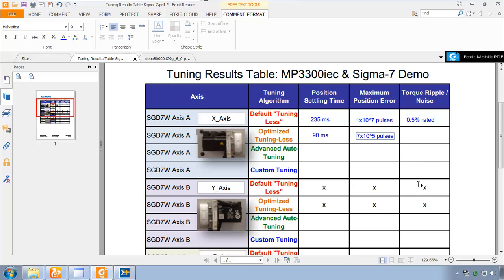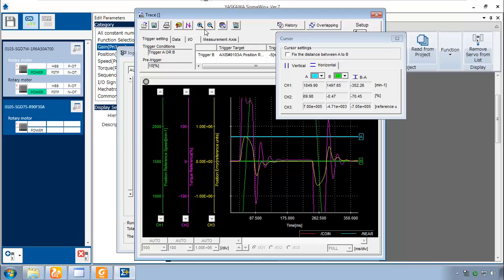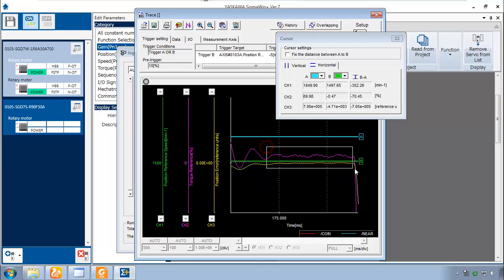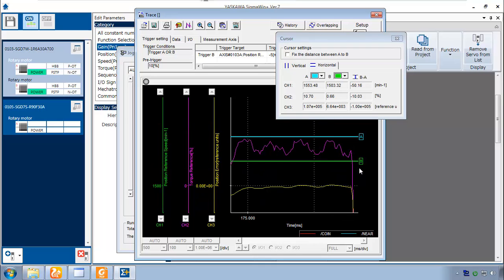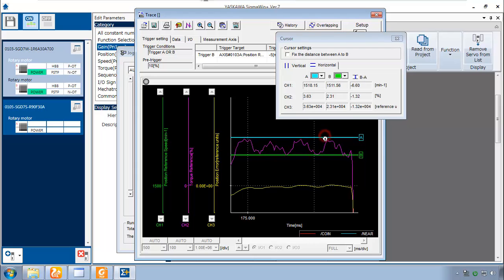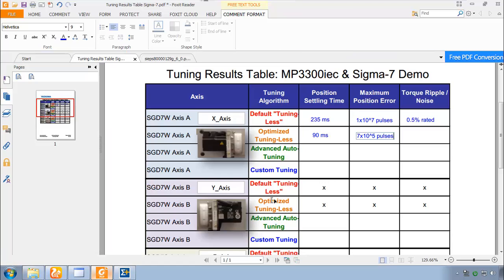And we're left now with a torque ripple to measure. Let me zoom in even closer on this torque reference. Looks like we do have some torque ripple now. It's gone up a little bit. From 0.5% to now it's 1.2%. I'll write that in here. 1.2% rated.